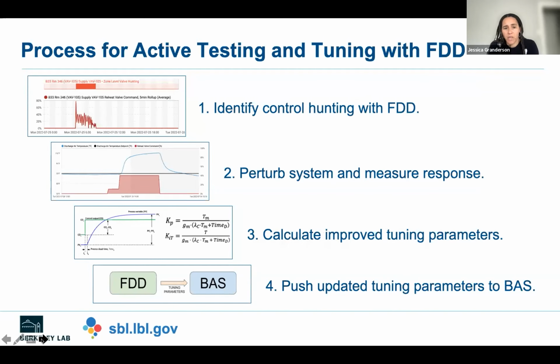So a couple more words on how we do this. The fault diagnostic tool identifies the fact that we have hunting here, that this valve is doing the open, close, open, close, open, close thing. We then go in and we perturb the system actively through that read-write BAS capability. We measure the response. So here we're looking at the process variable and the control parameters. Then, with the knowledge of the specific PID equations that are configured for this controller, we can calculate the improved tuning parameters. And we push them back to the BAS through this two-way capability. The test then ends. We're able to confirm through the software that we have indeed eliminated that hunting condition.